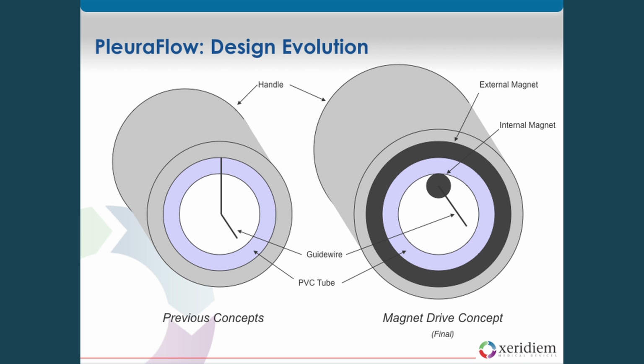With this concept, we have an internal magnet that communicates with an external magnet. You have a magnet on the inside of this tube and a magnet on the outside of the tube. The magnet on the inside is anchored to the clearance wire, the loop that pulled the clot out, that's how that is controlled. The magnet on the outside is connected to the external handle.